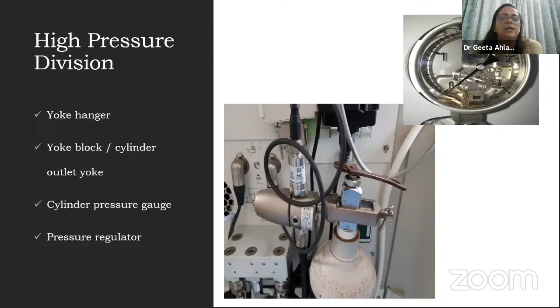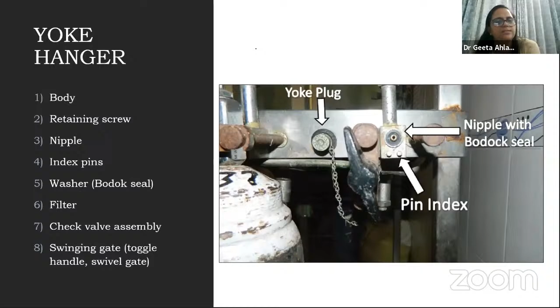To my postgraduate students, the first question you can be asked is, what is a yoke? I hope you understand what a yoke is. You must have seen a bullock cart where two bullocks have a yoke on them, and they are pulling a cart because of the yoke which connects them to the cart. So similarly, this yoke connects our cylinder to the machine. It has a body, a retaining screw, a nipple and the index pins, a washer between the machine and the cylinder with filters and check valve assemblies, and a gate which tightens it and keeps it straight.